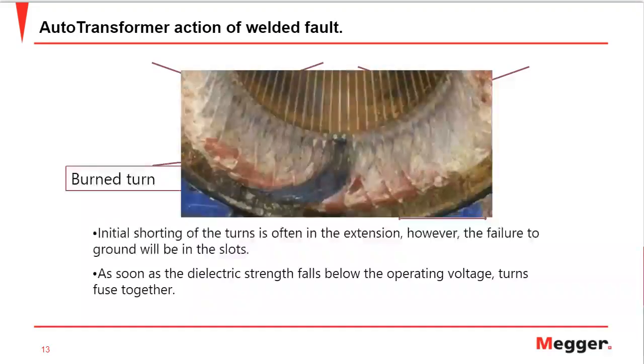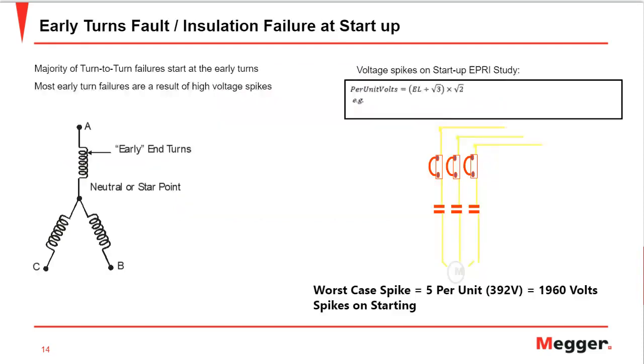As you can see, what probably would have started as a turn-to-turn fault eventually ended up as a slot liner to ground fault, which represents the burning effect on that coil. So moving ahead, we'll see why early turns have major faults and also the insulation failure at the startup.